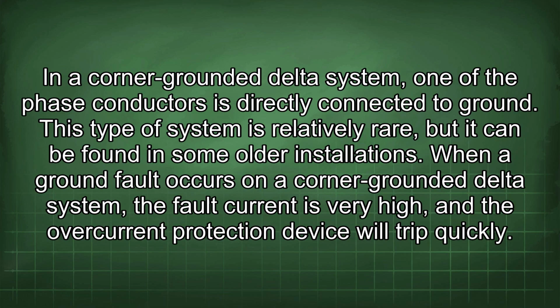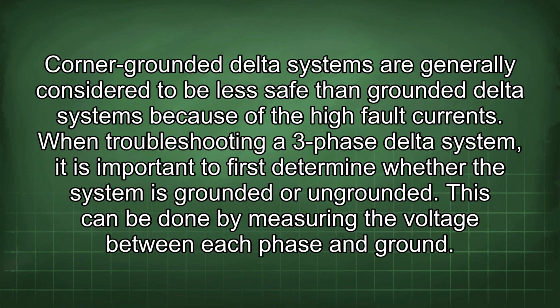In a corner-grounded delta system, one of the phase conductors is directly connected to ground. This type of system is relatively rare, but it can be found in some older installations. When a ground fault occurs on a corner-grounded delta system, the fault current is very high, and the overcurrent protection device will trip quickly.